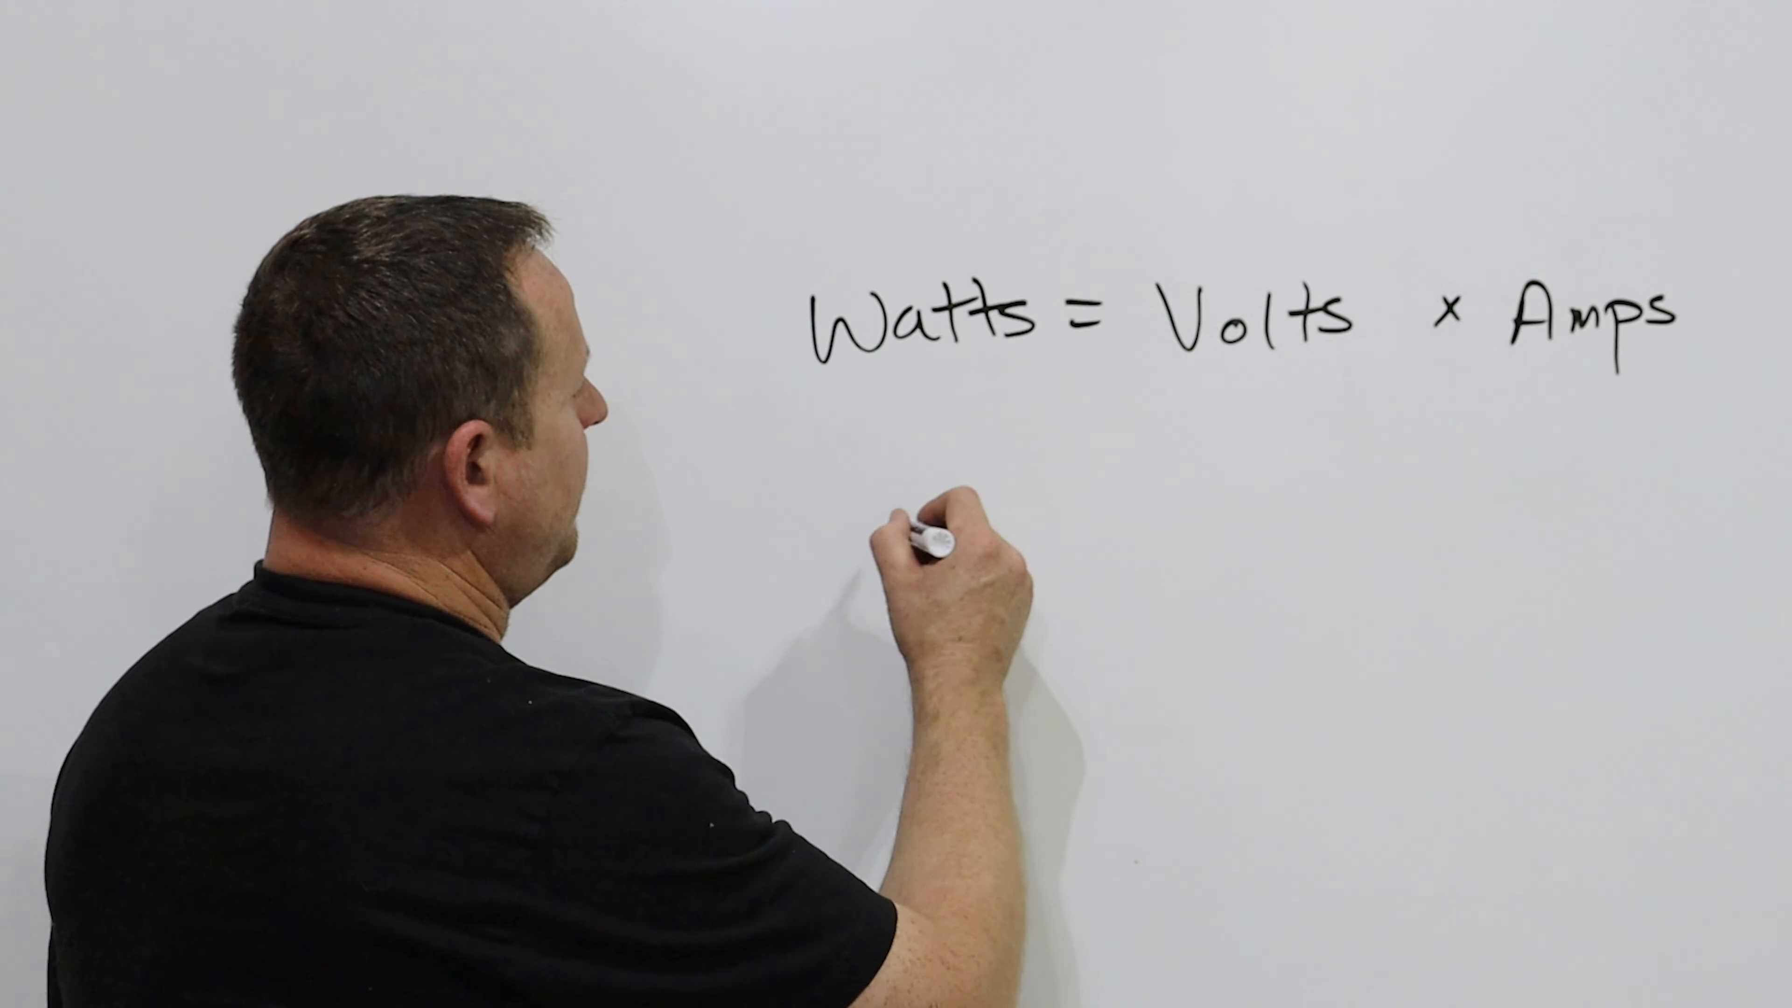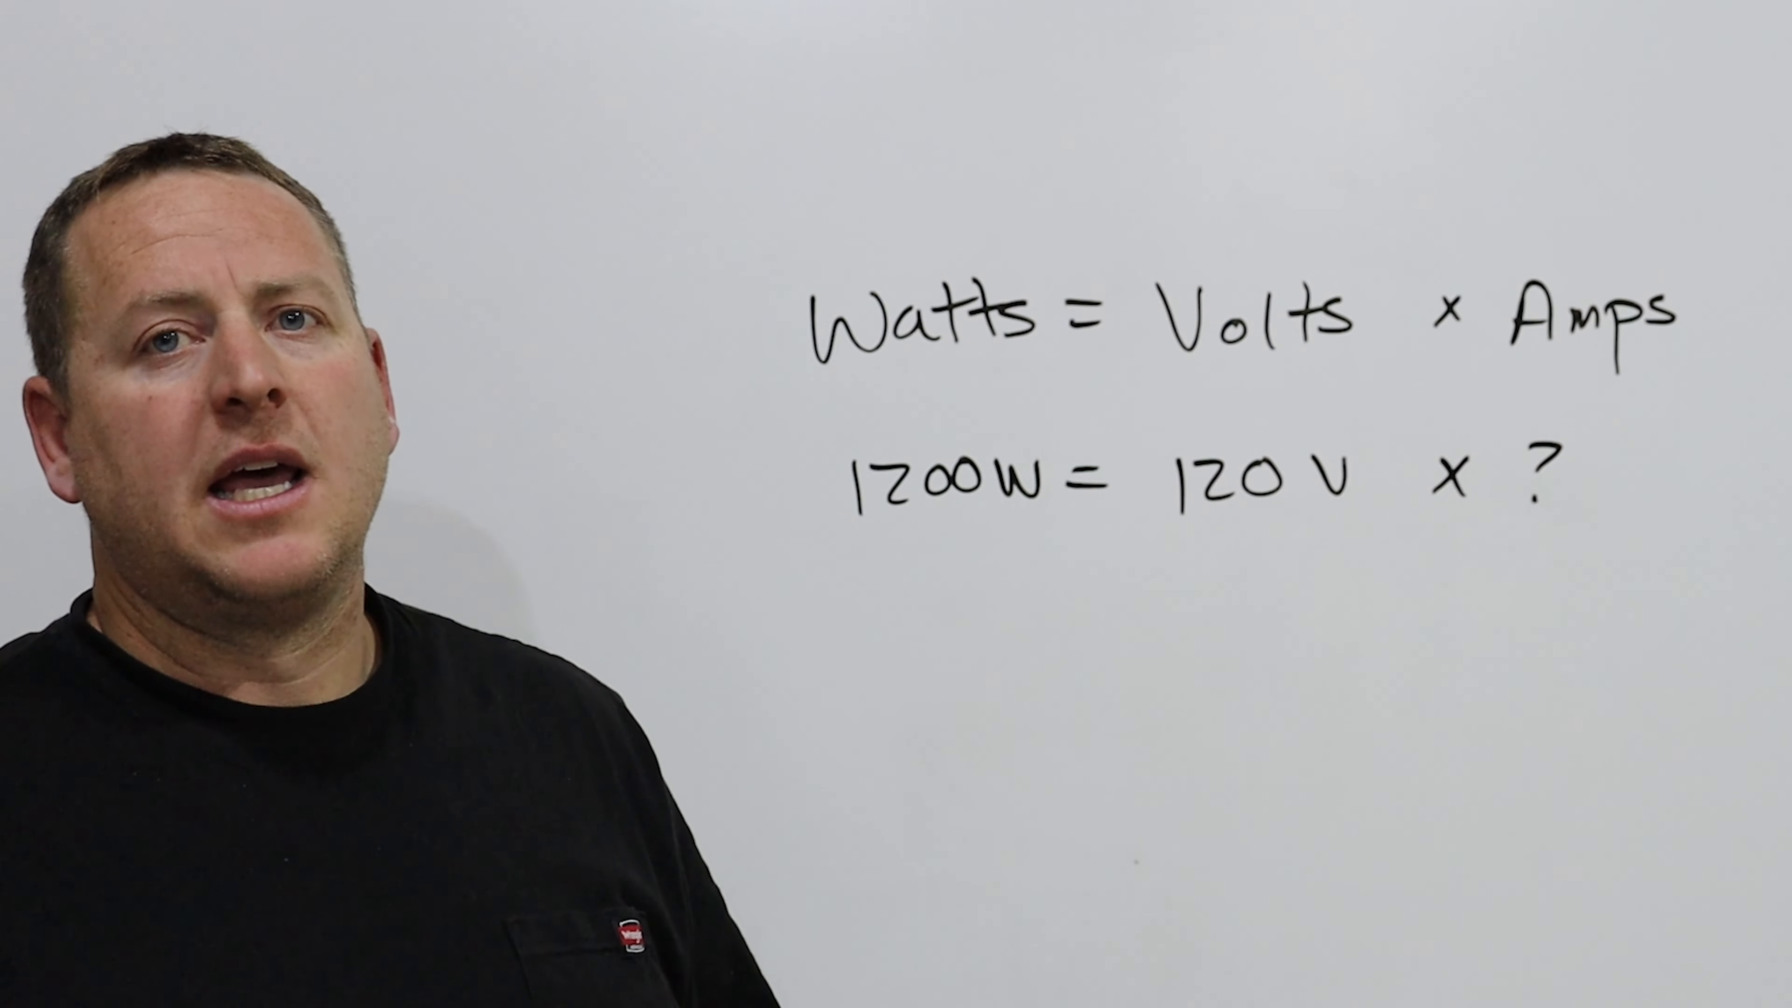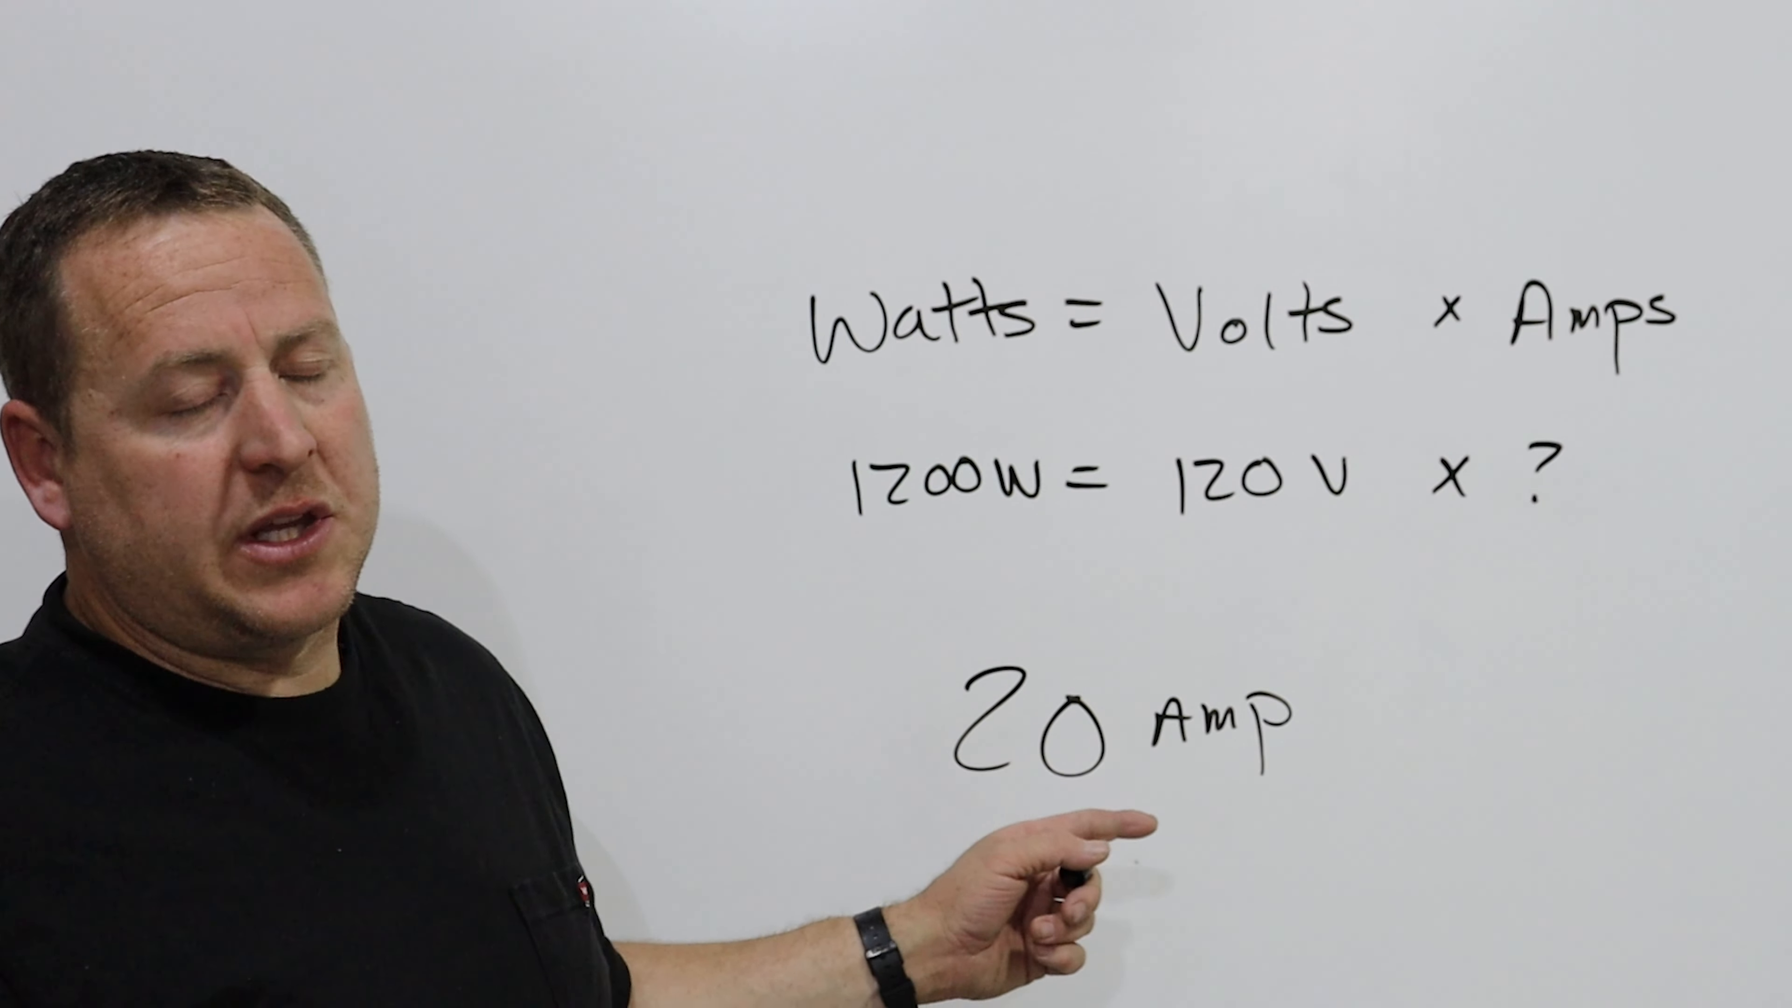If we have 1200 watts, we know the voltage is 120 volts because we're using a 120 volt circuit in our home. Now we need to figure out how many amps we're going to run. Why this is important: I talked about a 20 amp circuit, and obviously we don't want to draw more amps than our circuit is capable of carrying.